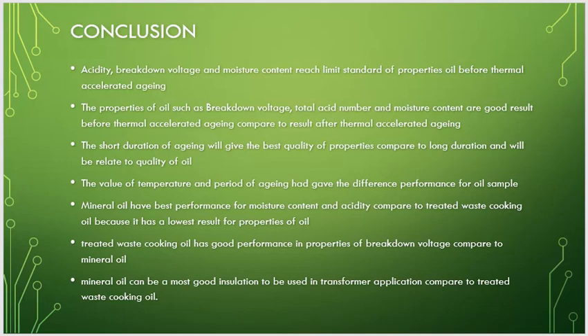Mineral oil has the best performance for moisture content and acidity compared to treated waste cooking oil because it has the lowest results for oil properties. Treated waste cooking oil has good performance in breakdown voltage compared to mineral oil, and mineral oil can be the best insulation to be used in transformer applications compared to treated waste cooking oil.